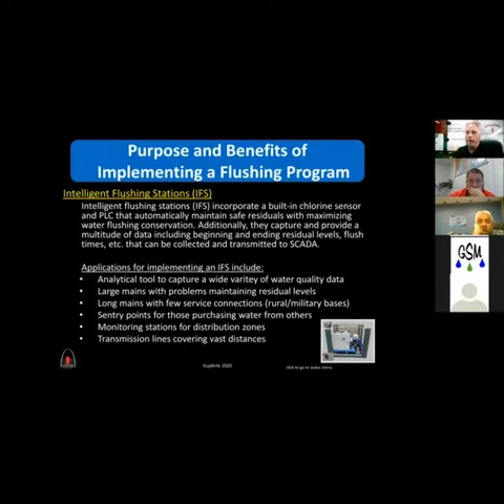What intelligent monitoring and flushing does is take that automatic flusher to the next level, where now I have a PLC and a chlorine sensor that takes samples of water, and I only flush based on the residuals I want to maintain.